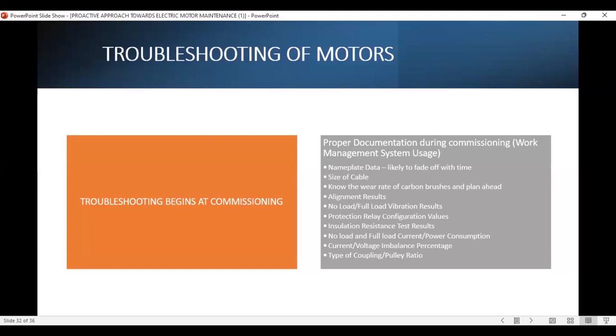And your protection relay configuration values also have to be kept so that in future troubleshooting, you know that during commissioning, the temperature setting was at this, the cooling time was at this. So what happened? What changes have come into place? So the initial protection relay values have to be kept in your work management system so that you are covered and you know where to refer to during troubleshooting.